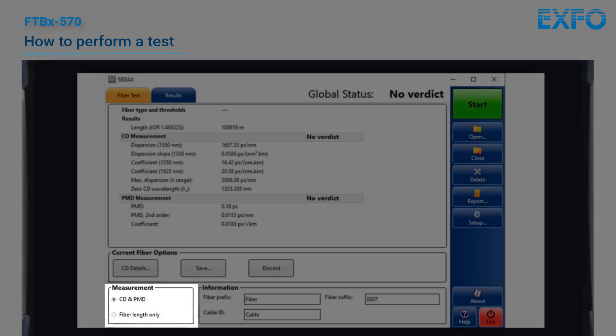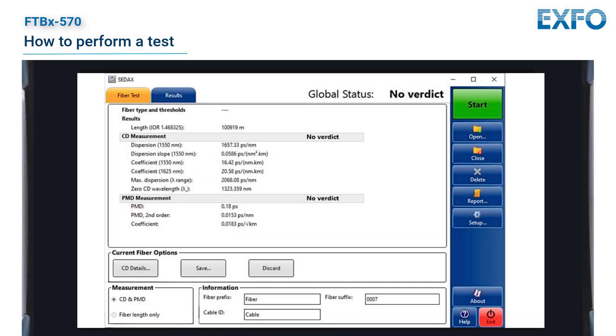Verify that the fiber under test is properly connected and that the setup is appropriate. It is important to note that the fiber under test must be terminated with at least a UPC connector. If there are high losses in the fiber, the fiber under test can be terminated with a mirror.